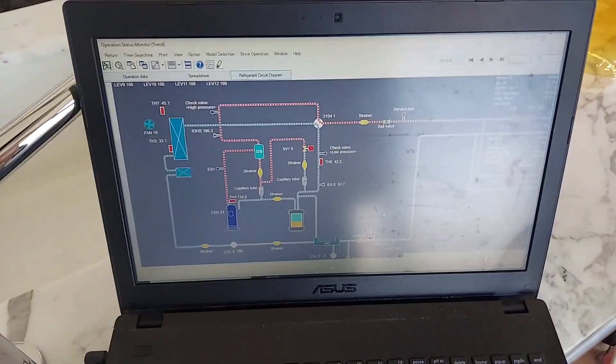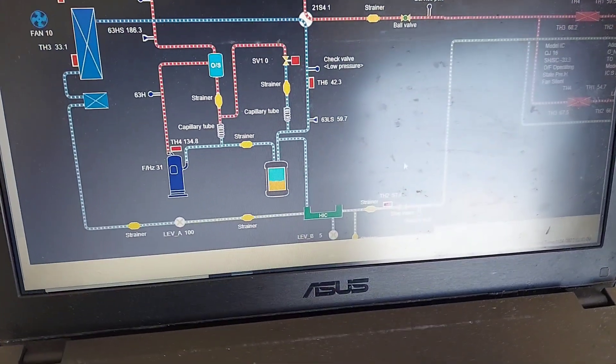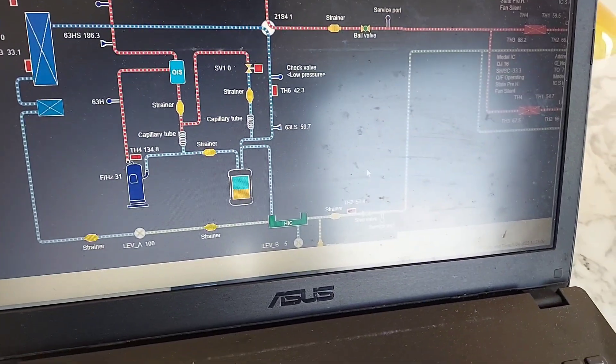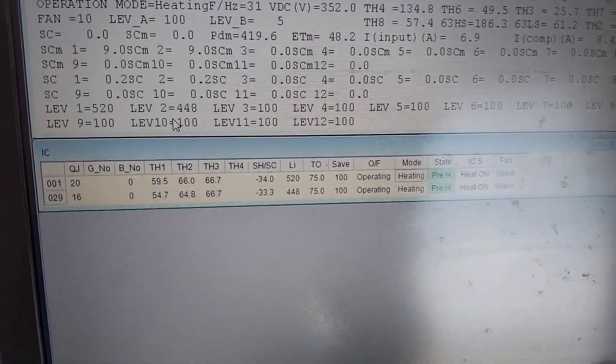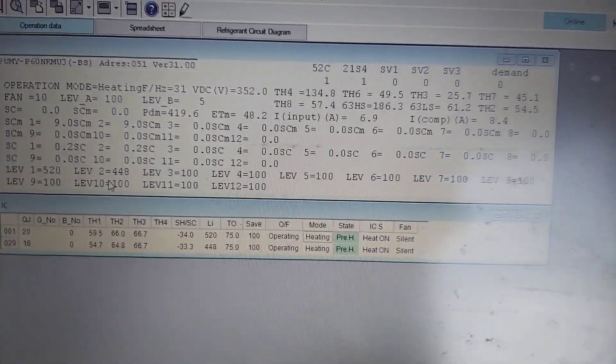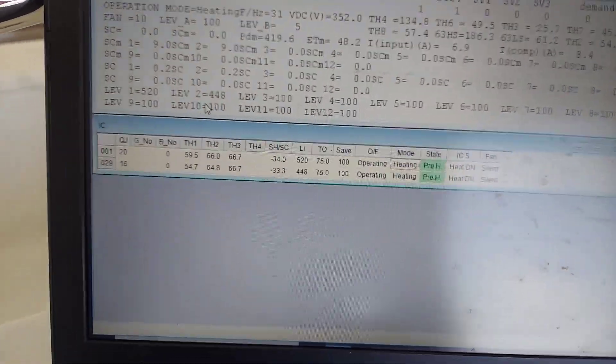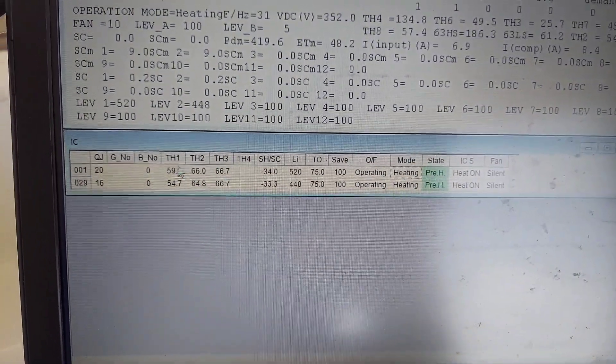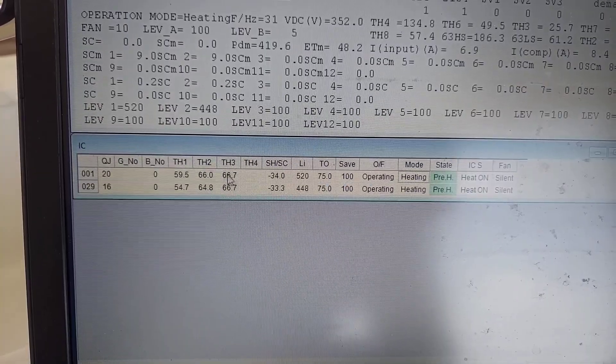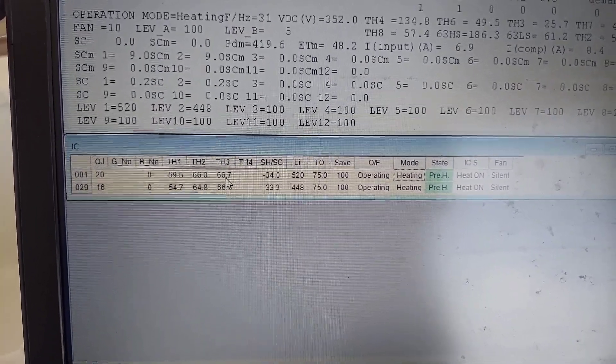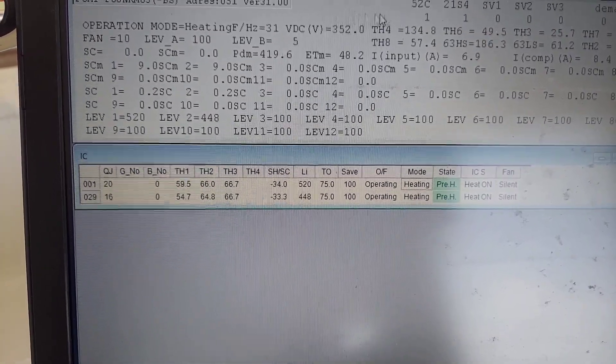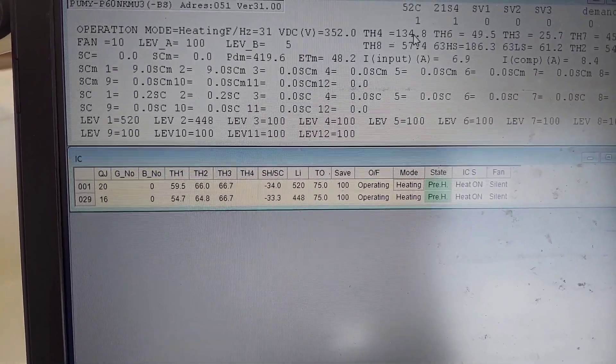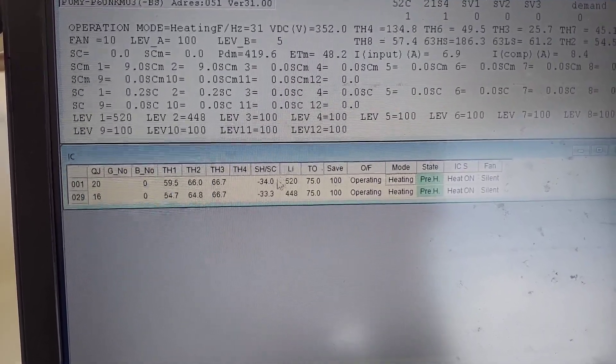And most likely what I'm going to be doing is just adding some refrigerant and then see how the response. But from experience I could tell you this is low refrigerant. Here goes that, so my TH3 is only 67, but TH4 right here is at 134 and yeah, it's a huge difference.